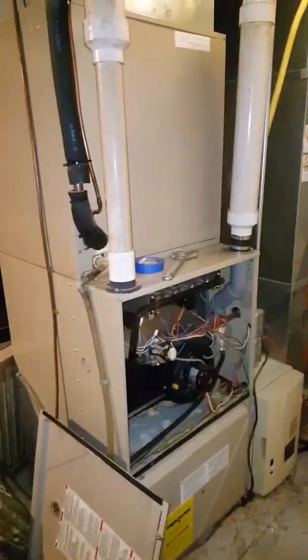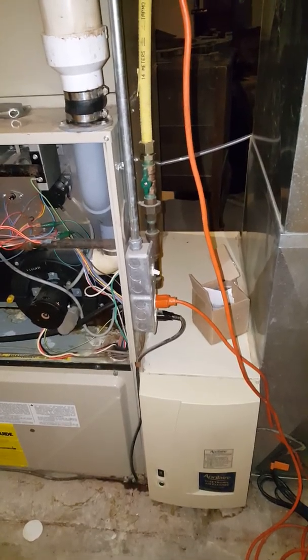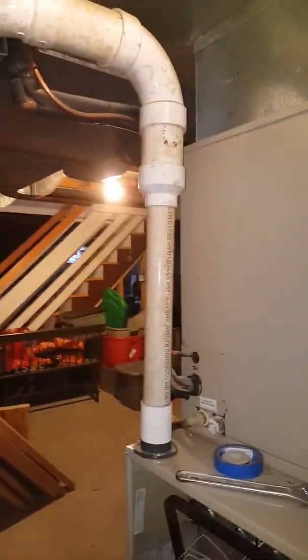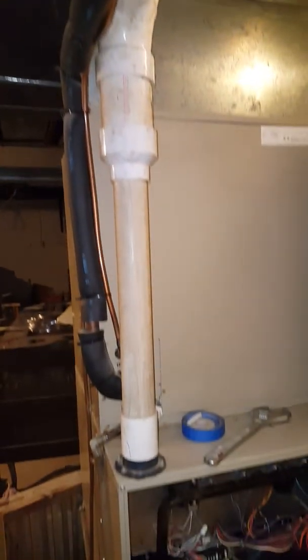We're looking to replace the furnace only at this time — furnace and media filter. We're going to go back with the same AprilAire 5000. We've got a 40-inch tall furnace, 3-inch PVC and 2-inch. We're going to cut the pipe loose here and here and then just reconnect to it with the new unit.